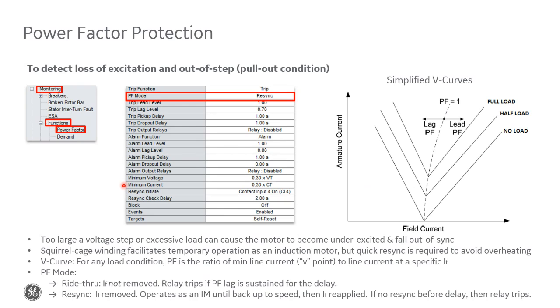The last protection element I wanted to highlight is the power factor element. We know that the load, the excitation current, the stator current, and the power factor are all closely related. The motor data sheets usually express this relationship via something like these V curves shown on the right. This is just a general example.